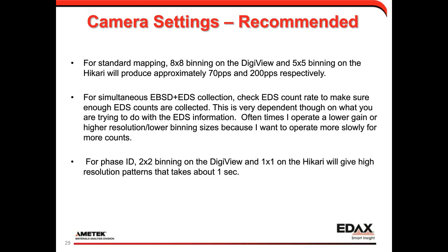Again, for phase ID, I'm going to use 2x2 binning, and 1x1 binning on the Hikari, because I need those high resolution patterns. If I don't have those high resolution patterns, I'm kind of going around what I need to do. That's mainly the basics of our camera settings, and I want to talk a little bit about backgrounds and how to use different backgrounds because, again, it's something I often see, people sometimes using the wrong background for different things.